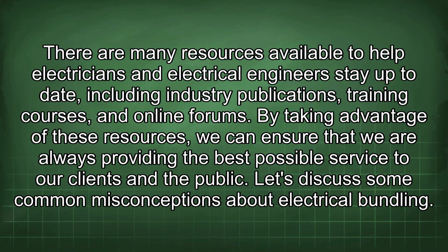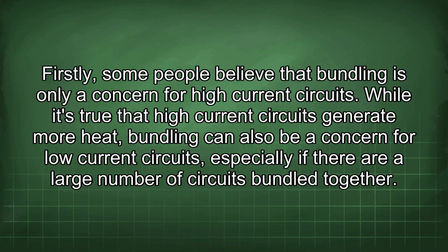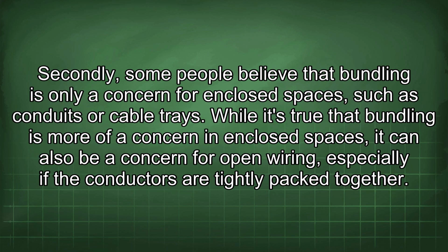Let's discuss some common misconceptions about electrical bundling. Firstly, some people believe that bundling is only a concern for high current circuits. While it's true that high current circuits generate more heat, bundling can also be a concern for low current circuits, especially if there are a large number of circuits bundled together. Secondly, some people believe that bundling is only a concern for enclosed spaces, such as conduits or cable trays. While it's true that bundling is more of a concern in enclosed spaces, it can also be a concern for open wiring, especially if the conductors are tightly packed together.